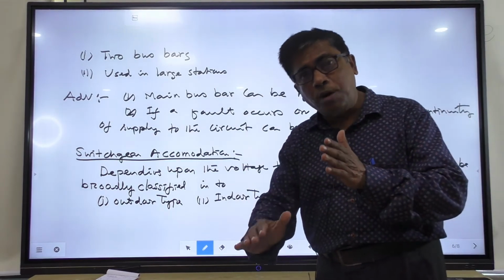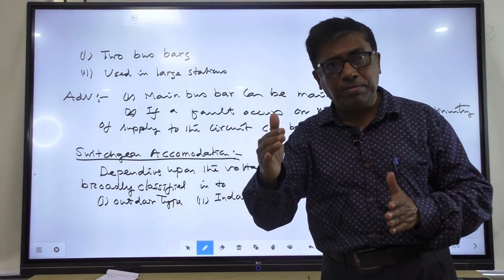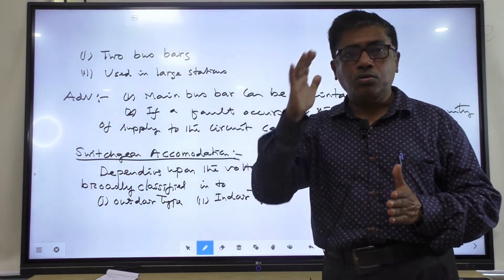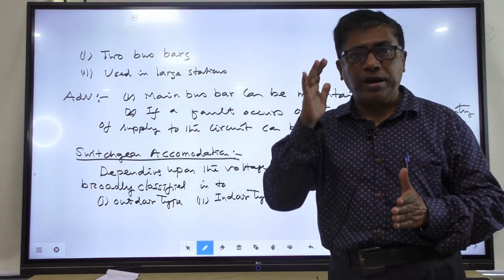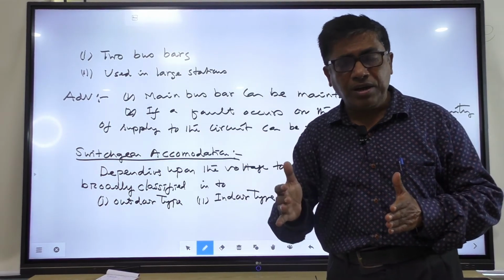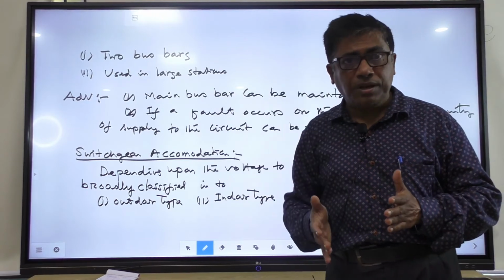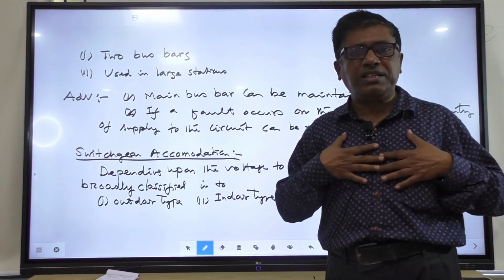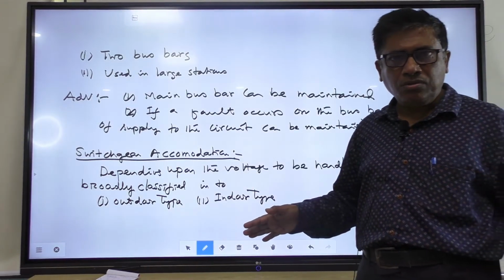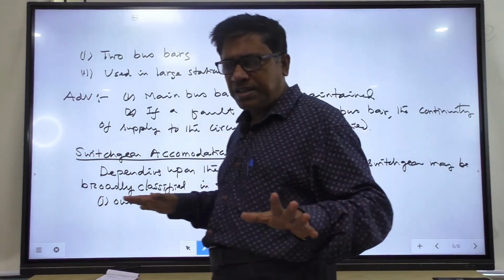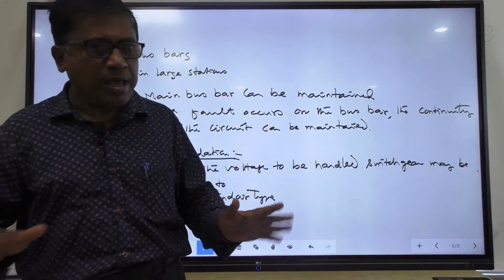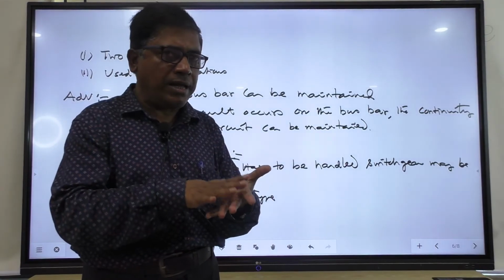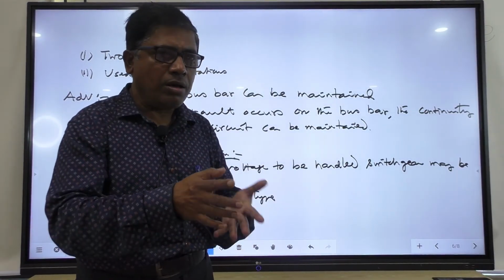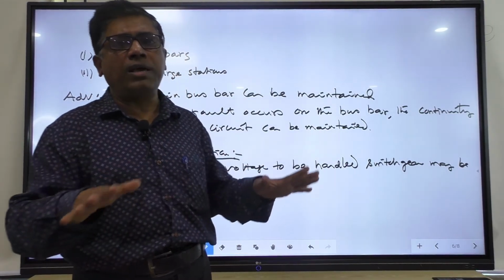below 66 kV, we are preferring indoor type substation. Voltage above 66 kV - 66 kV, 132 kV, 220 kV, 400 kV, 750 kV, 1000 kV, 1250 kV - this is line voltage, what I am discussing about the line voltage, don't get confused. Whatever I am discussing is about the line voltage. If the range voltage is above 66 kV, we are using the outdoor type of substation.